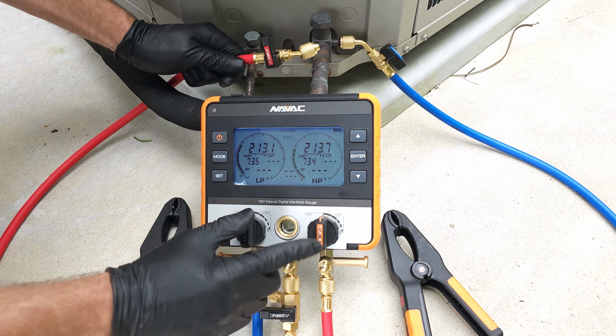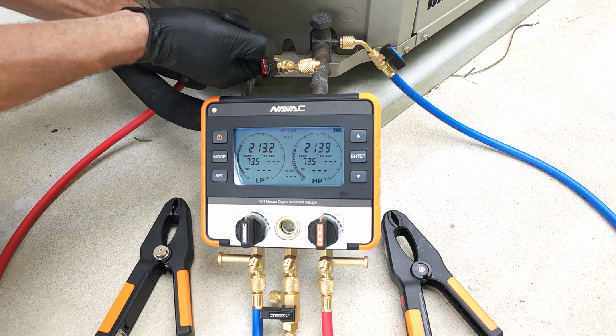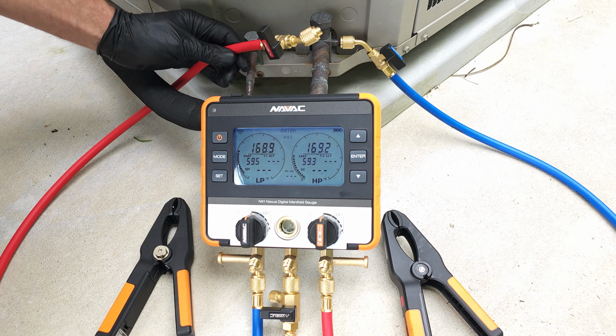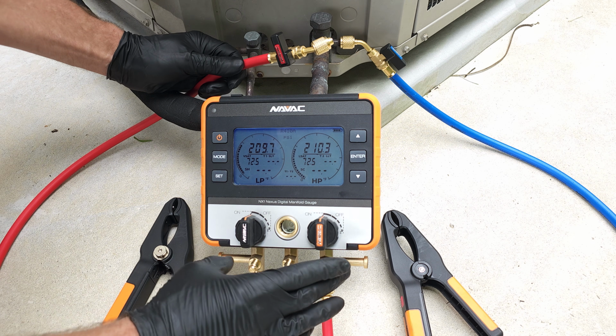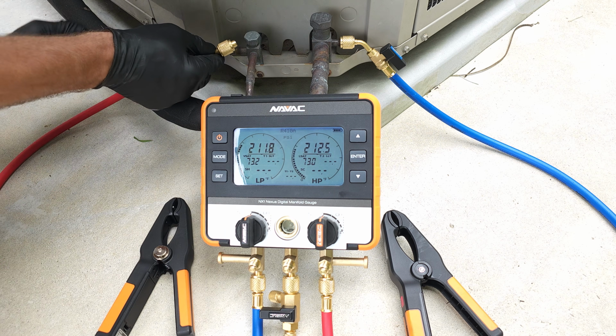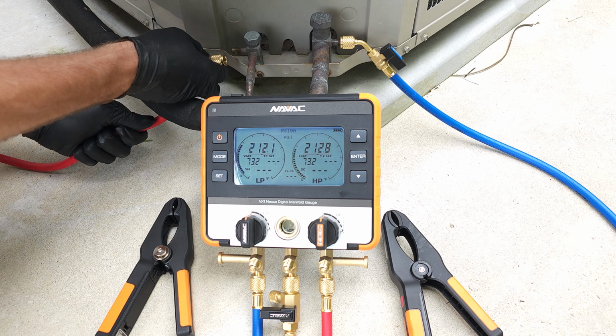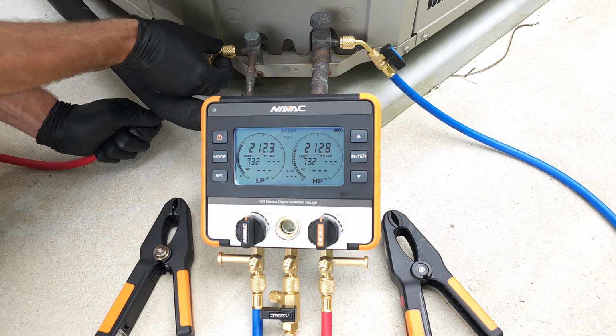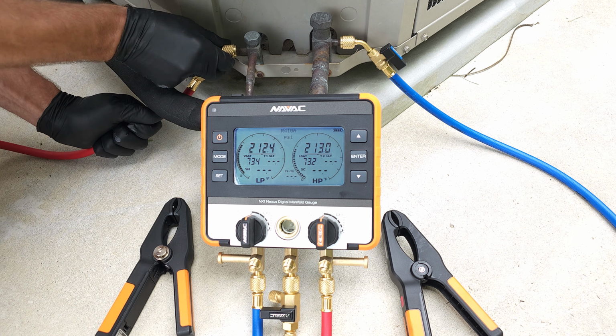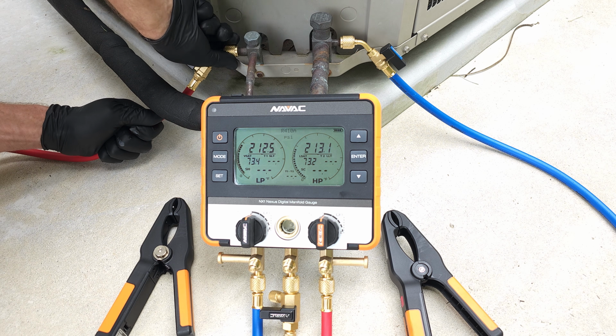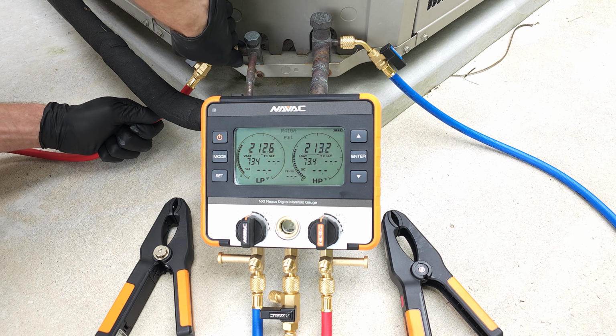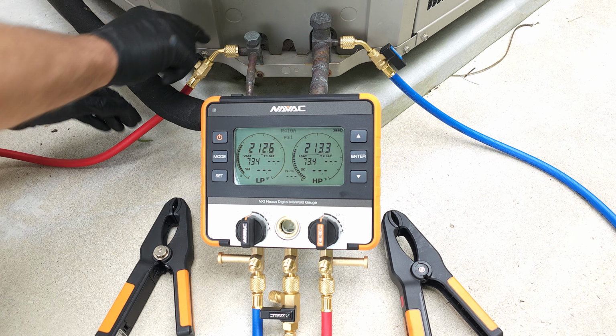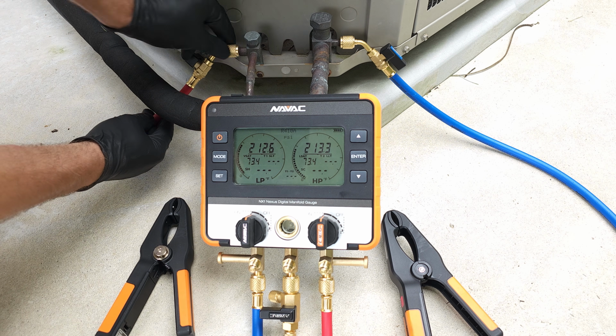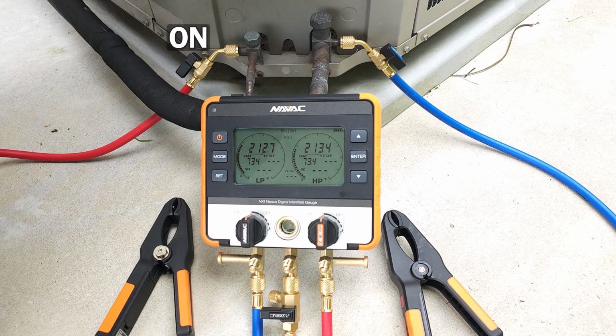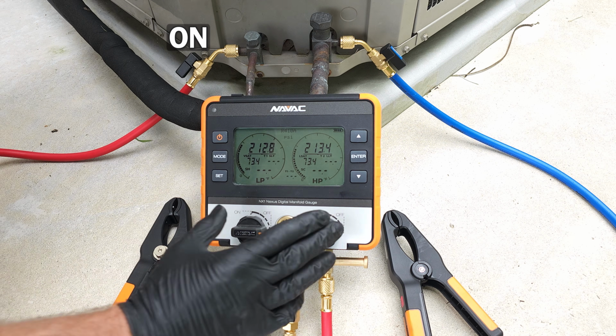So now, since these are both on, we can purge the air out. Now all the air is out of both hoses and the manifold, and we can go ahead and connect our red hose in here. We can turn this valve to the on position. We're also going to turn these off.